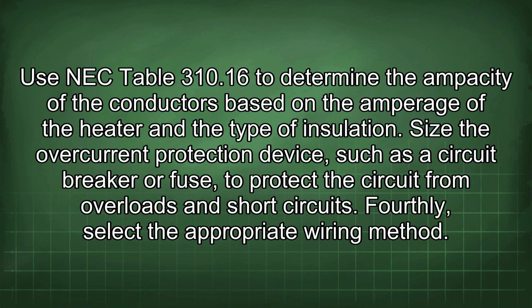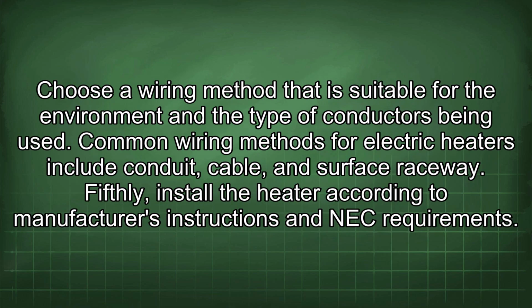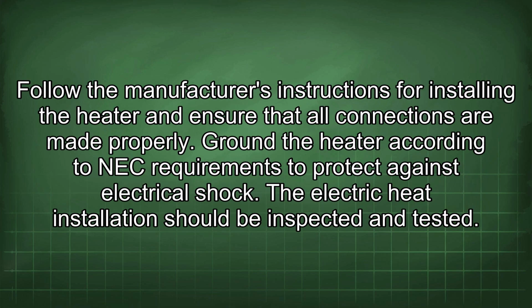Use NEC Table 310.16 to determine the ampacity of the conductors based on the amperage of the heater and the type of insulation. Size the overcurrent protection device, such as a circuit breaker or fuse, to protect the circuit from overloads and short circuits. Fourthly, select the appropriate wiring method. Choose a wiring method that is suitable for the environment and the type of conductors being used. Common wiring methods for electric heaters include conduit, cable, and surface raceway. Fifthly, install the heater according to manufacturer's instructions and NEC requirements. Follow the manufacturer's instructions for installing the heater and ensure that all connections are made properly. Ground the heater according to NEC requirements to protect against electrical shock.